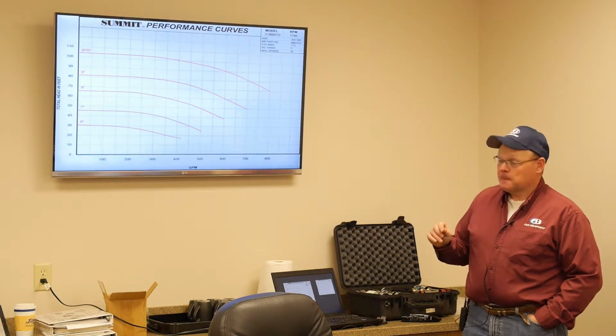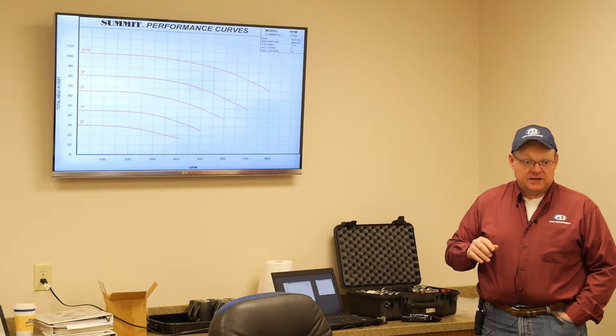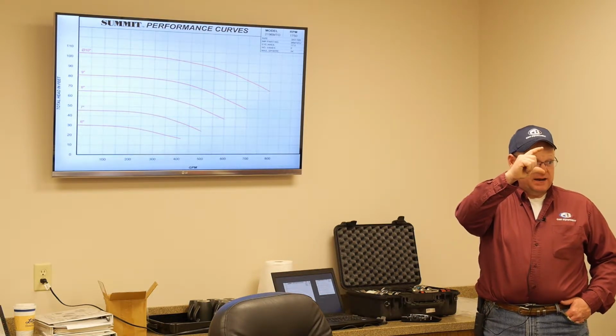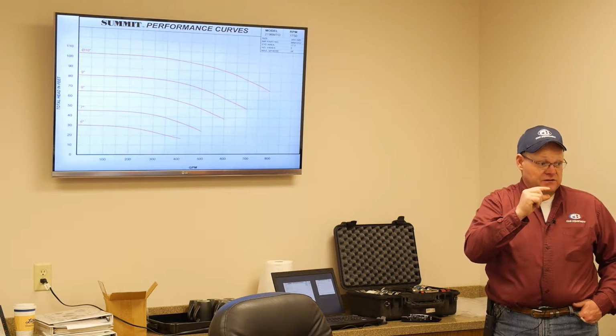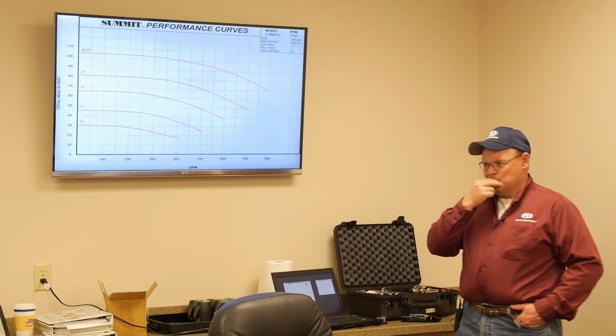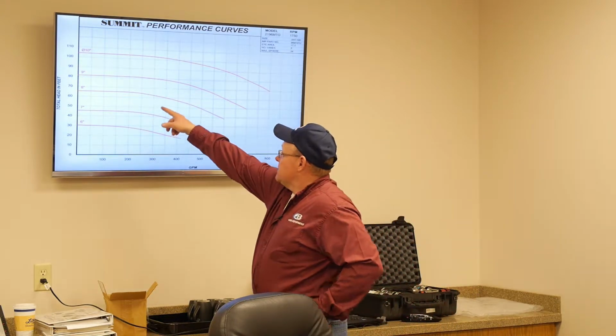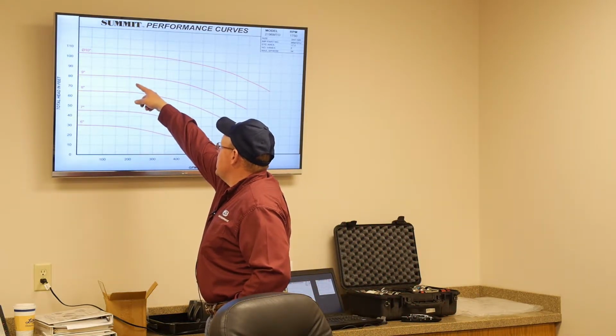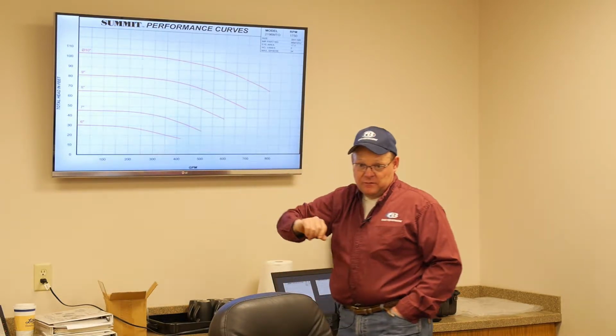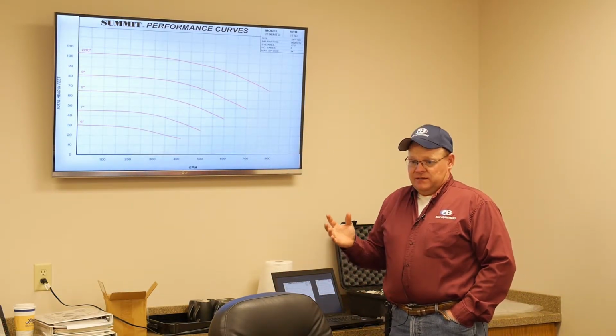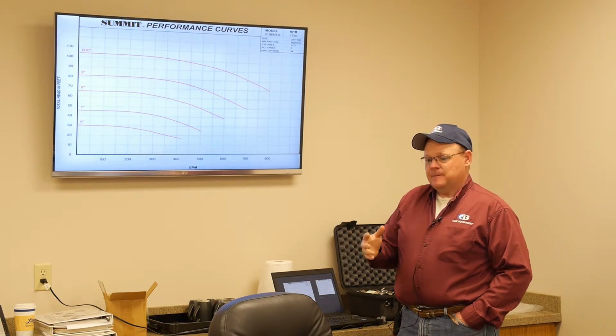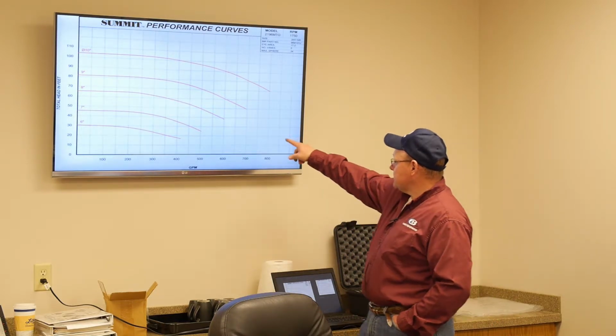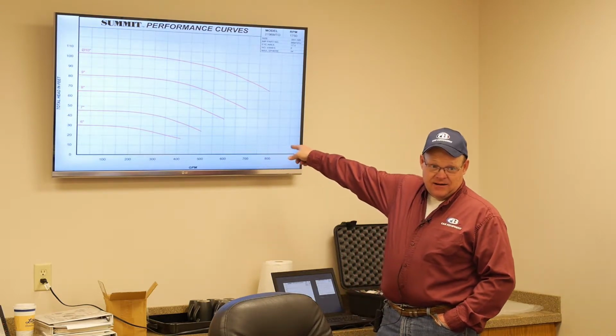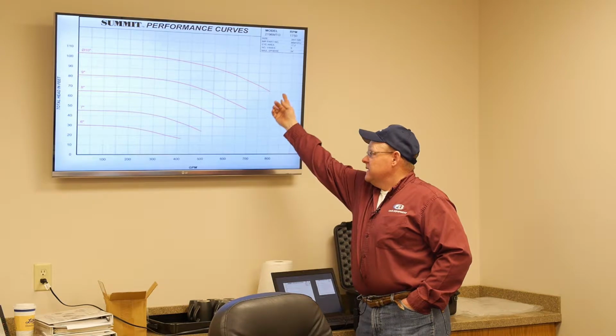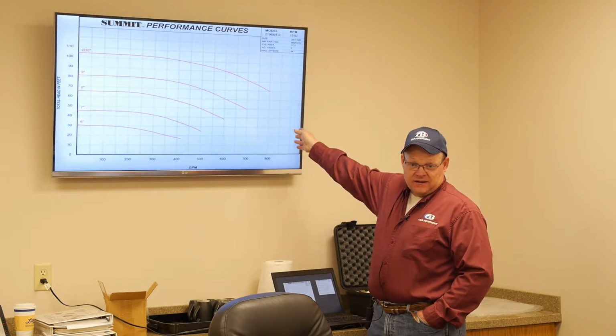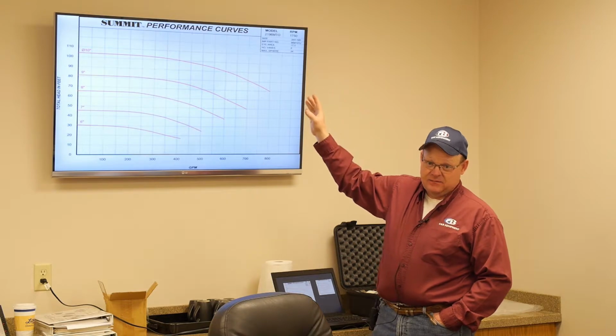But now more of a gap on your cutwater? Yeah, yes, you're opening up the gap between your cutwater. So in turn it probably lowers the efficiency, and we'll get to that in just a minute. Okay, so now take whatever it was, 200 or 82 pounds divided by 2.31. About 36 pounds, 37 pounds. 35.49. But we can't even get to 800 now, right? Because it's the end of the curve. If you run it off the end of the curve, bad things happen. It just does, things never come out good.